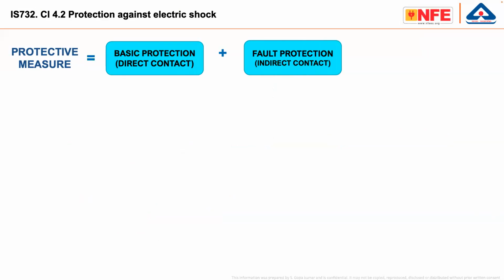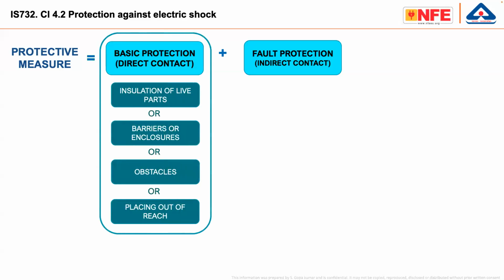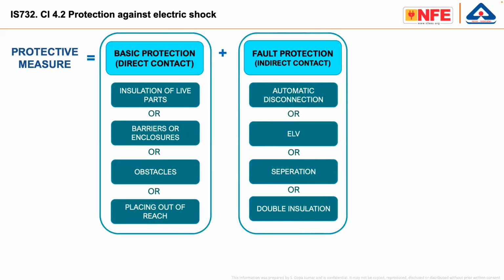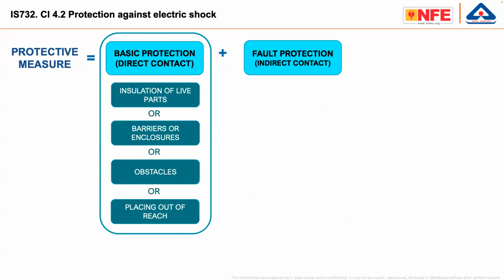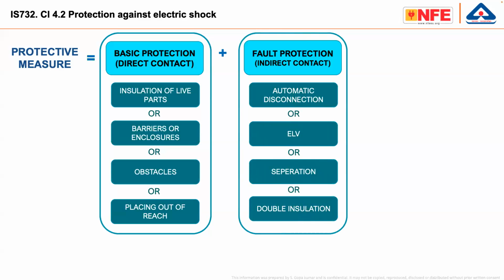Now, if you look at the IEC classification, a lift is a machine where ordinary people are using it, as well as skilled people carrying out maintenance of the machine. Protection against electric shock is achieved by basic protection plus fault protection. Both are necessary. Basic protection consists of insulation of live parts, barriers, enclosures, obstacles, and placing out of reach. These are the different methods. Fault protection: in an installation with very good basic protection, in case of a fault, people may get a shock, because somebody touching a faulty device may get a shock. In order to avoid shock, fault protective measures are required. The established fault protective measures are automatic disconnection, extra low voltage separation, and double insulation.